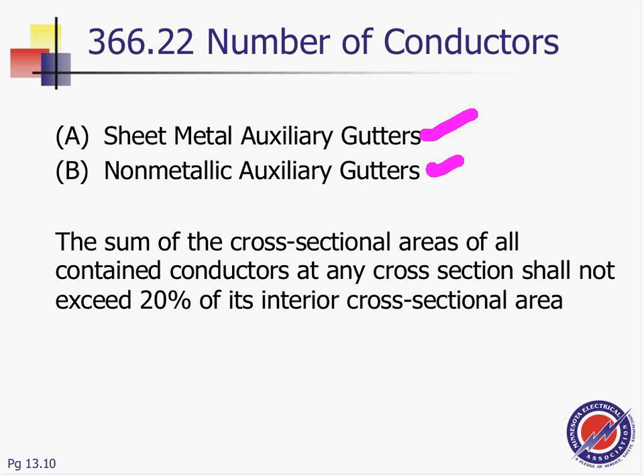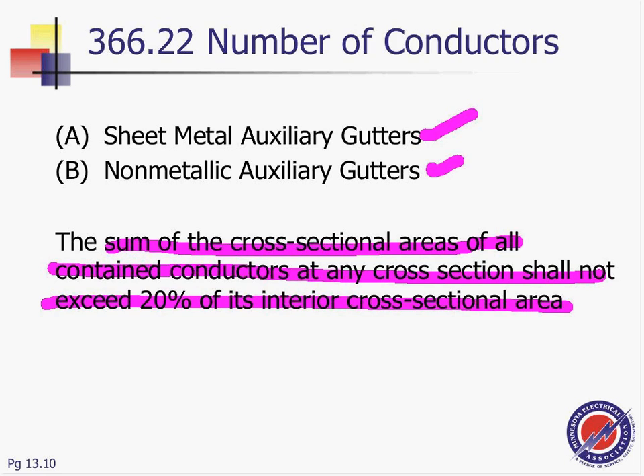The sum of the cross-sectional area of all the conductors shall not exceed 20% of the gutter's fill. So they don't want you to fill more than 20% for this baby. You're not permitted to fill more than 20% of it. So the sum of the cross-sectional area shall not exceed 20%. The adjustment factor shall apply only where the number of current-carrying conductors exceeds the limit. So that's basically that 20% fill. No more than 20% fill. How do you apply this, my friend?